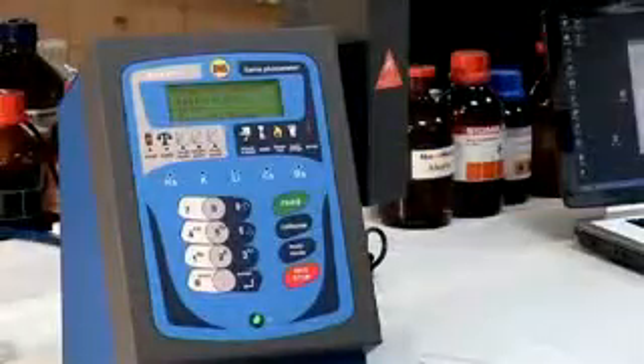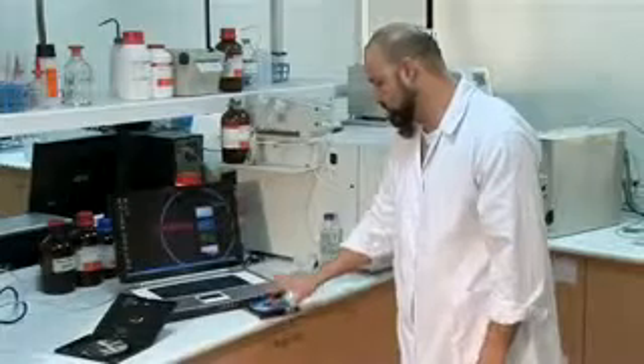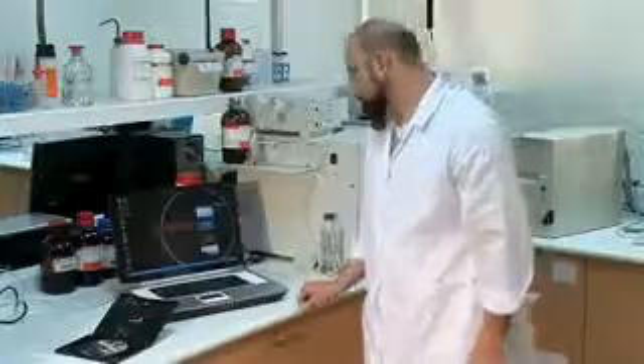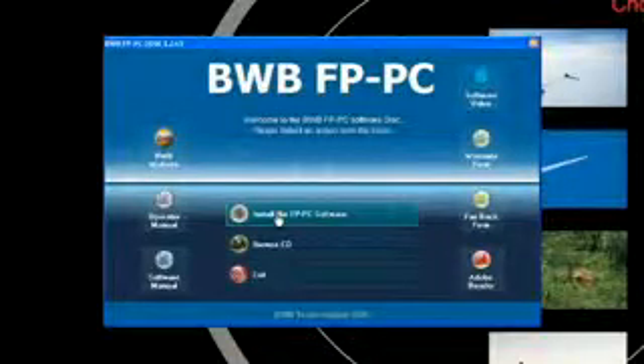The Bwb Xp is easy to install. First of all, connect the gas tubing to the regulator. Now connect the waste tubing to the drain cup and run it to a drain. Attach the nebulizer to the mixing chamber, the air to the front barb and the gas to the side barb. Attach the power cord to the Bwb Xp and the power outlet, and finally, just add gas.